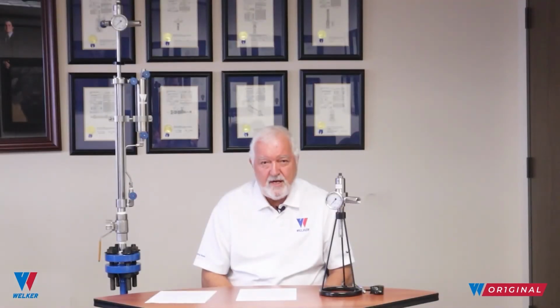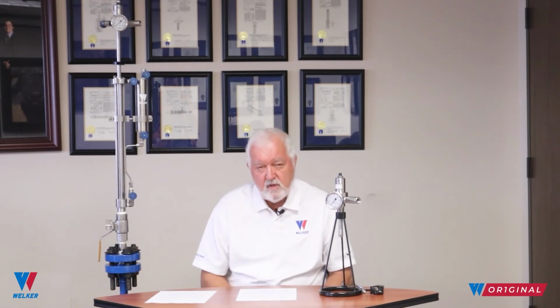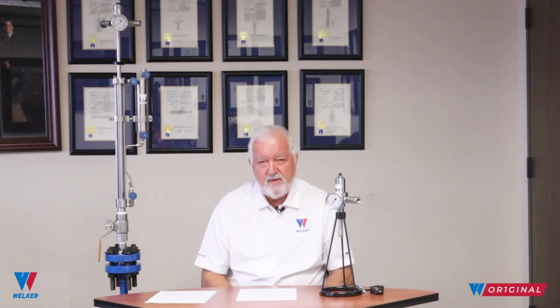Others have designed similar probe regulators for this industry, introducing tips at the bottom that shed hydrocarbon liquids and water from the flowing stream to prevent them from reaching the analyzer. Welker also provides such a tip, but with the clear understanding that shedding liquids in the pipeline—ensuring only natural gas at flowing conditions reaches the analyzer—lets the BTU value of those hydrocarbon liquids go by undetected and unaccounted for. People need to be aware that this is what happens as a result: preventing free water and free liquids from reaching the analyzer also prevents awareness of the BTU value of the hydrocarbon liquids in the pipeline.